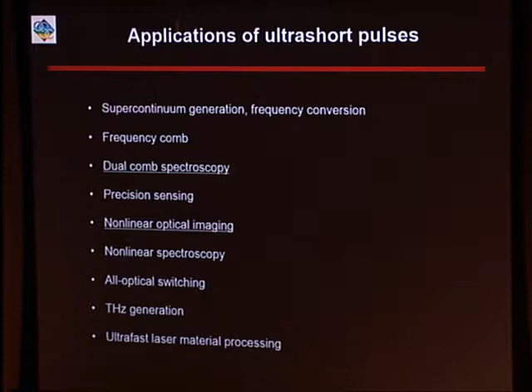Dual-comb spectroscopy is a very interesting technique to measure an absorption spectrum, for example, with very high resolution and very short acquisition time, right? The technique is similar to Fourier transform spectroscopy. In Fourier transform spectroscopy, you send the laser source in, and then you split that into two, right? Then you combine them back together, and you change the delay. You get an interferogram, and then you do the Fourier transform. You get a spectrum back, right? If you put a sample in one arm, then you can get the absorption spectrum that way.